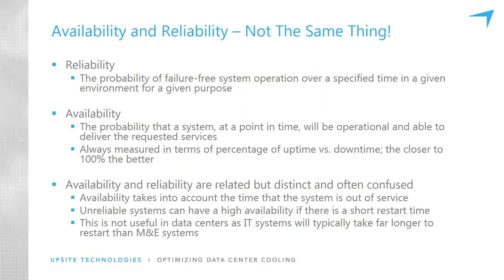We tend to use the terms availability and reliability somewhat synonymously, but they're actually not the same thing. Reliability is the probability of a system operating failure-free over a period of time. Availability is the probability of a system being operational throughout a period of time. They are related but distinct and often confused. When talking about data centers, we should really be talking about service availability rather than just reliability.